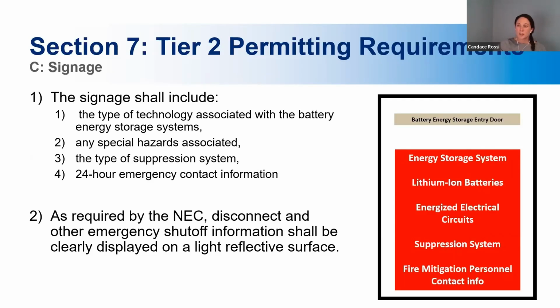Next is signage. This highlights the signage required by the code, doubling down to make sure everyone's aware of it in the law as well. The sign needs to show the type of technology associated with the battery, any special hazards, whether a suppression system is involved, 24-hour emergency contact information in case something goes wrong, and as required by the NEC, disconnect and other emergency shutoff information shall be clearly displayed on a light reflective surface. This ensures that whether the system is installed indoors or outdoors, people are aware it's a storage system and of the potential hazards. You definitely don't want an unmarked door in the middle of a field or in an office building granting access to the storage systems for unauthorized people.